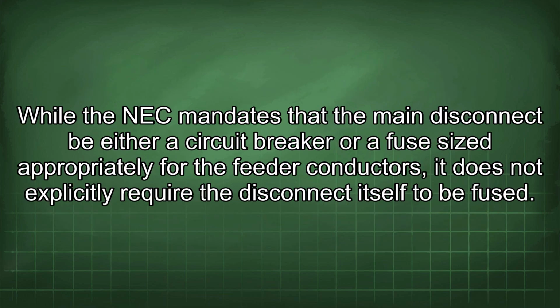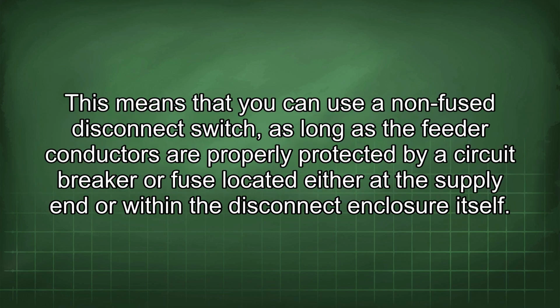While the NEC mandates that the main disconnect be either a circuit breaker or a fuse sized appropriately for the feeder conductors, it does not explicitly require the disconnect itself to be fused. This means that you can use a non-fused disconnect switch, as long as the feeder conductors are properly protected by a circuit breaker or fuse located either at the supply end or within the disconnect enclosure itself.